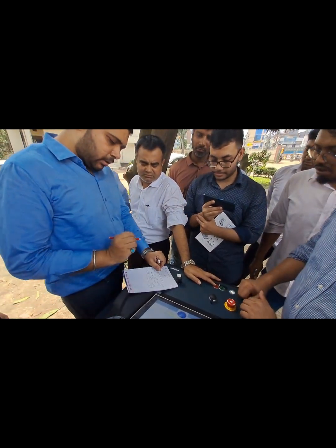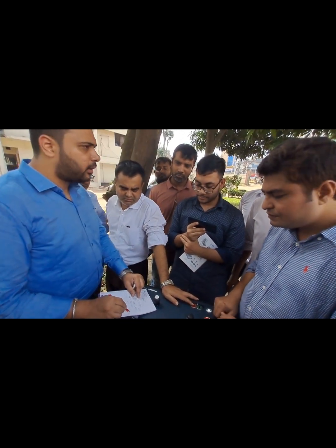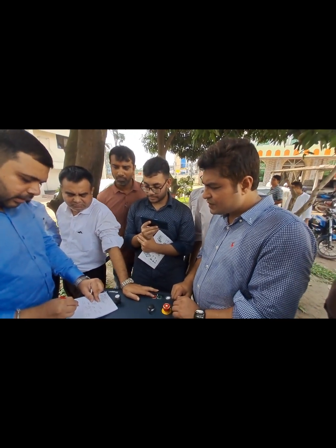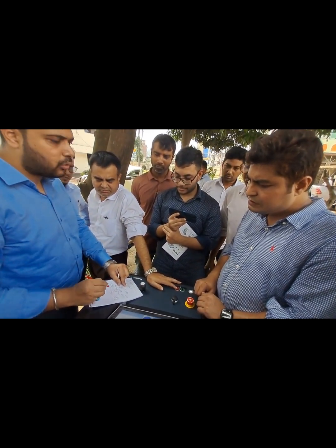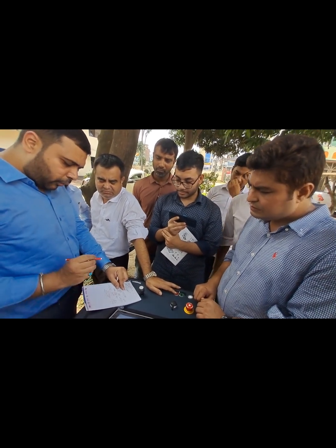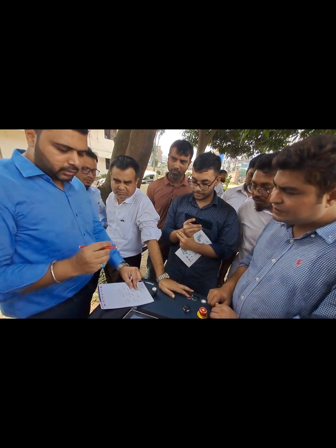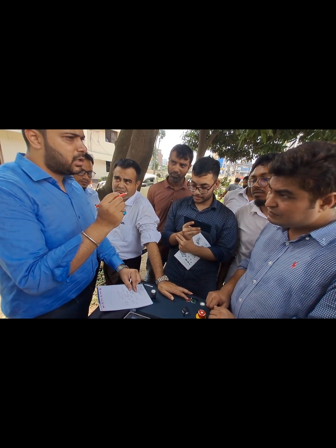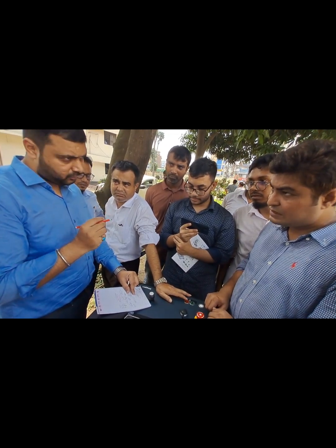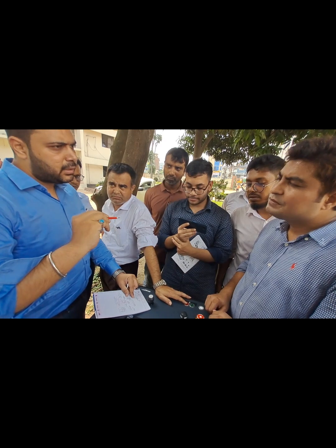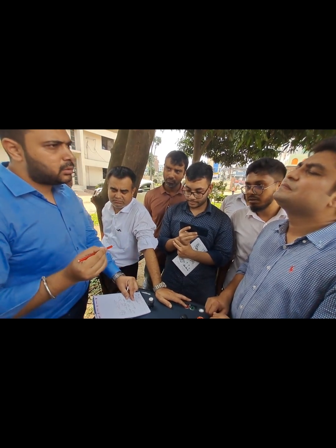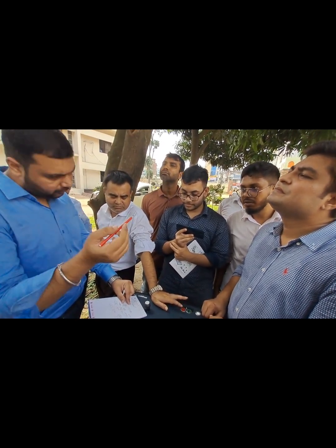So let us consider it is a short circuit fault. Resistance values are less than 100 ohm. So what is the principle of TDR? TDR will inject a 100 volt pulse, 100 volt only. It will inject it into the cable and it will return through the path, from the conductor only.